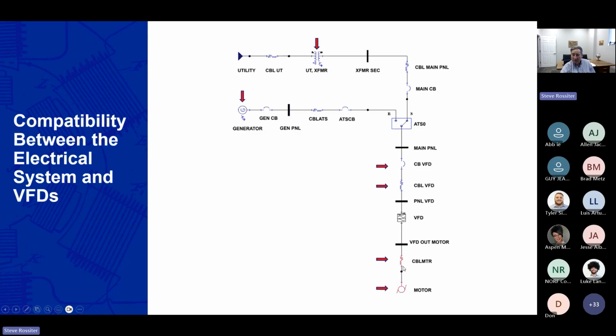From the output of the VFD, we'll also, like I said, talk briefly about the effect that the PWM waveform, that pulse width modulated waveform, has on the cable. And nowadays there's even an inverter duty cable that some manufacturers say you've got to have. You've got to solve this problem. Cables are usually pretty tolerant, but there are some situations where that really is a factor that needs to be considered, and especially in the motors.